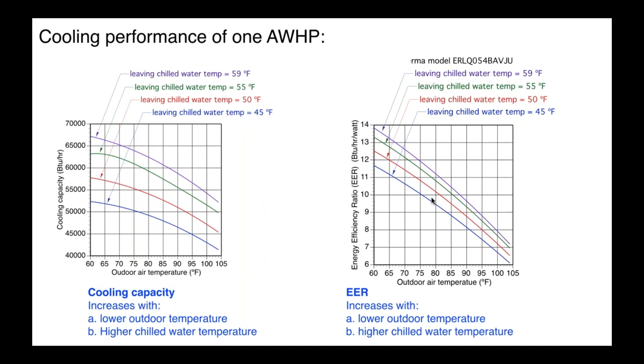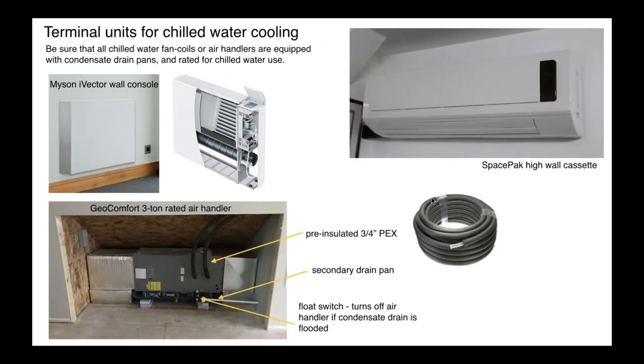Now, we do want to make sure that we size our coil so we get adequate latent cooling. We've got to make sure we get the moisture removal capability of whatever we're sending this chill water to, such that it can maintain a reasonable relative humidity. A typical target's about 50% RH at a 75 degree dry bulb indoor temperature. So again, a larger coil is going to benefit from the standpoint of keeping the chill water temperature elevated a little bit, and thus allowing the heat pump to operate at a higher capacity and also higher energy efficiency ratio.